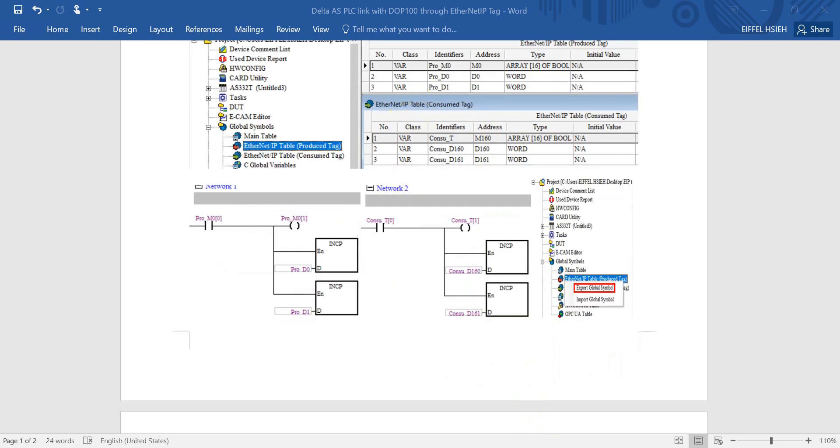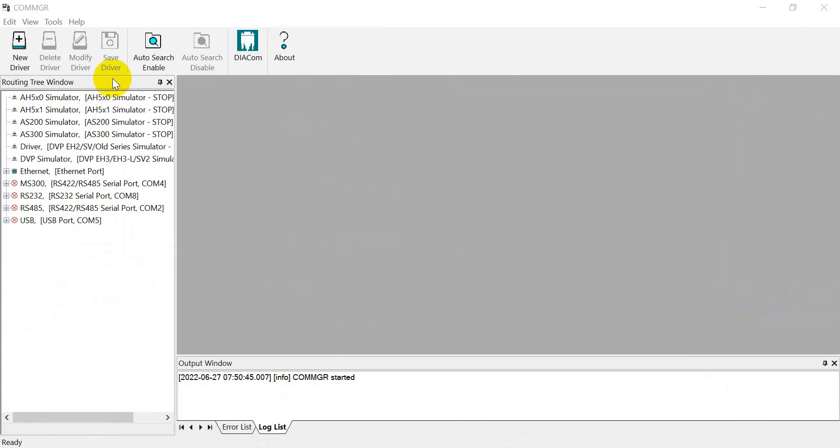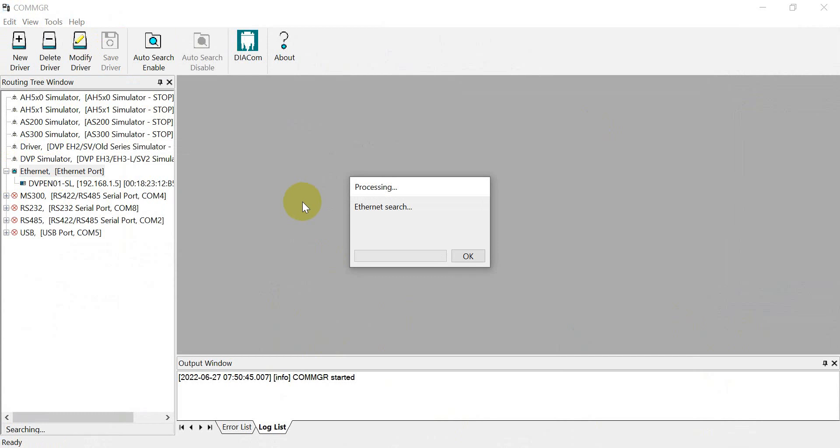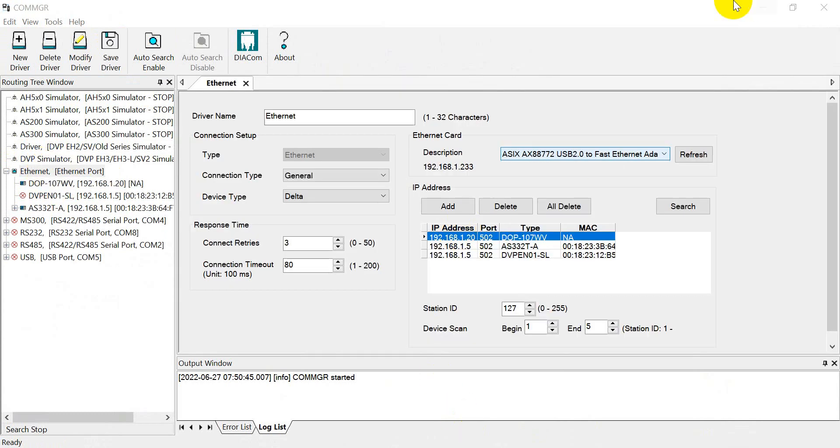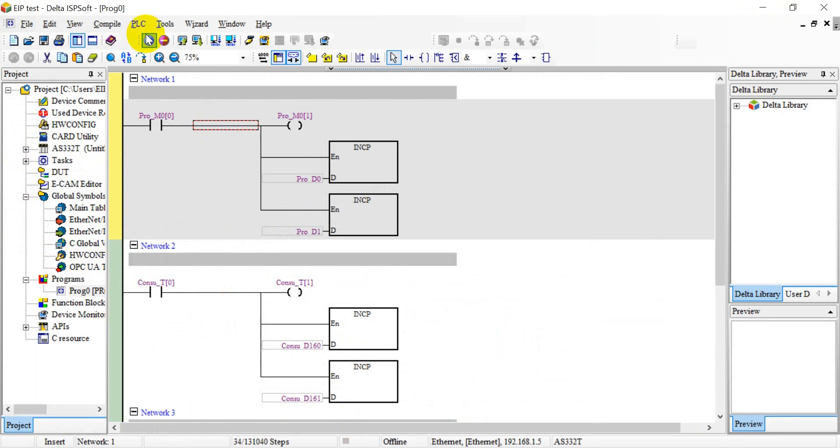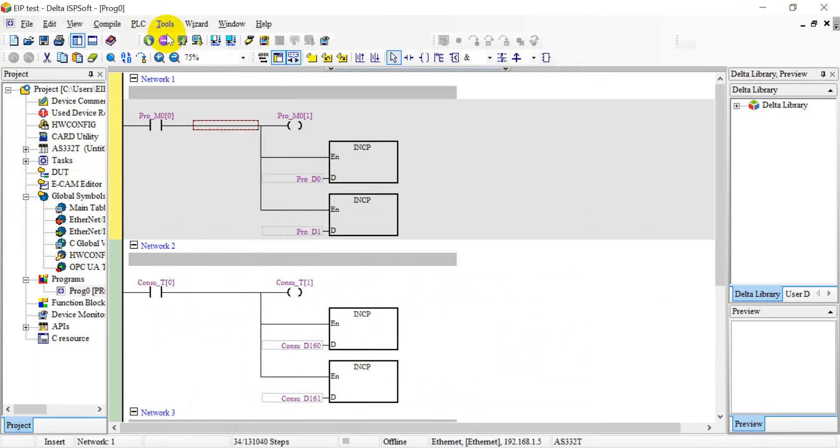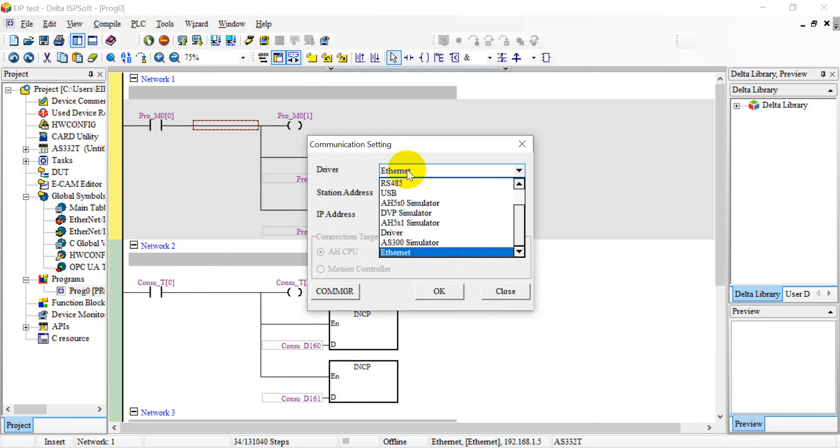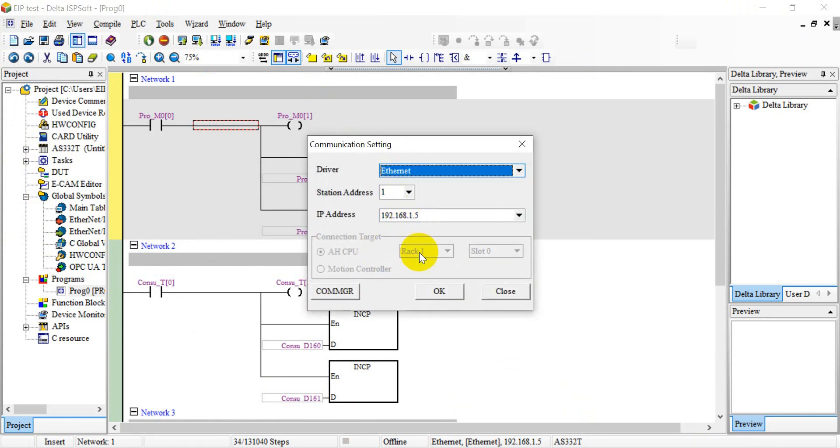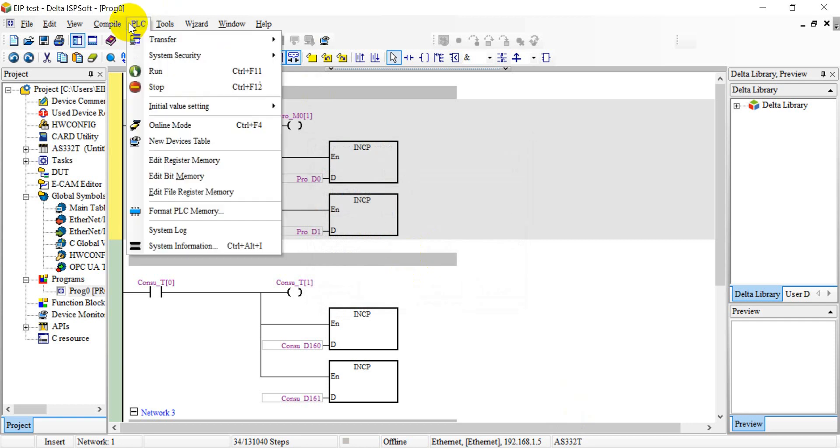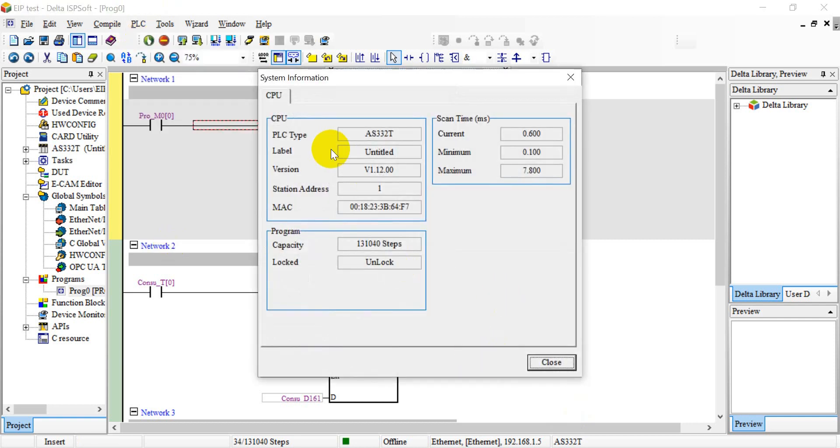Now we will switch to the software part, COMMGR to establish the connection. Because now we use the Ethernet, we can double click Ethernet. Here you will find the device that we connect to the network. Then we can go back to ISPsoft. Then go to the communication settings. Here we will select the Ethernet one and select the IP address of this PLC. Then we can go to the PLC and check the system information. You will see now we already established the connection.